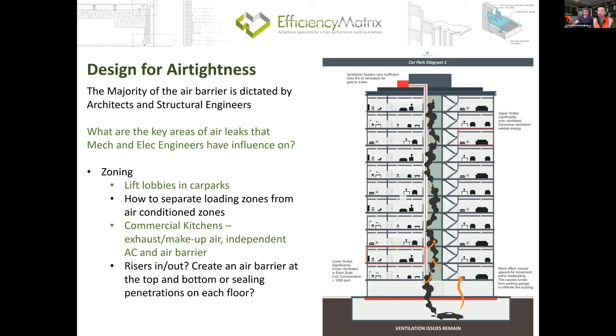And the other thing is risers. We all deal with risers as mechanical or electrical engineers. Whether the riser should be inside or outside the air barrier makes it very, very different. You either create a capping between the plant room floors or the top roof to create the air barrier at a smaller area. If you can see my mouse cursor, you can provide a capping at the top and at the bottom of your riser, so you minimize the area you need to treat as airtight.